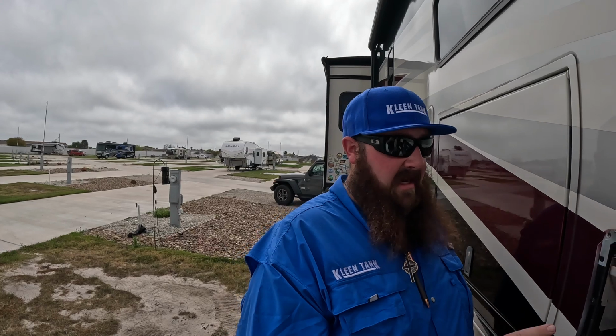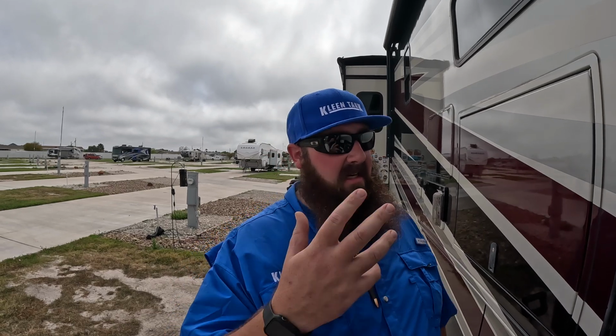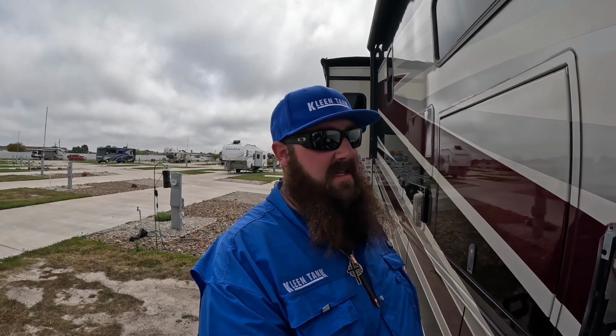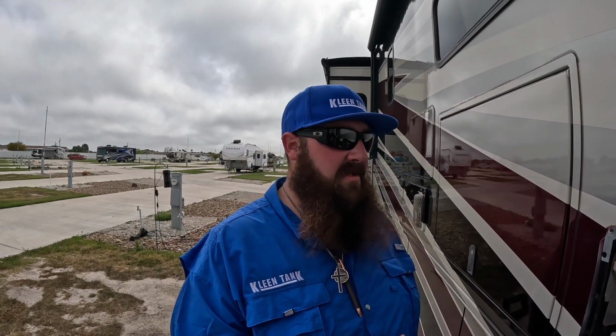Yeah, because our tank does not have an anode on it. Having an anode in there is a critical thing to have. That hard water is looking for something to eat. Yes, the tank itself may be glass lined, porcelain lined. Might be something that they state is bulletproof. It's going to be just fine. That may be true, but your electric heating elements and your burner tubes are still made out of aluminum, something for it to eat. That is direct contact. You don't want it eating through your elements, causing you bills to come through later down the road. Clean them out, replace your anodes, check your anodes, and make sure everything's good to go.